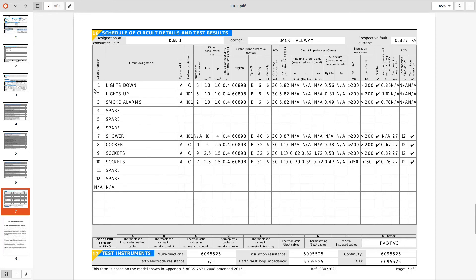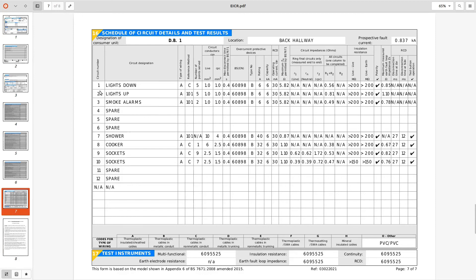Moving on, the schedule of test results. Lights downstairs, lights up, smokes, some spare circuits, shower, cooker, socket sockets. No mention of an RCD on here but it's got to fall in, we've got some kind of figures in this column so it's a split load board, probably a Wylex board. I might see the main switch on here just because I'd just like to see what it is, what the main switch is 60439 947 whatever it might be. You can put your mains tail sizes on the first line and give any other information relevant to that particular installation. It's DB1, it's in the back hallway. 837 is prospective fault current and from that we can work out the voltage would be 242.